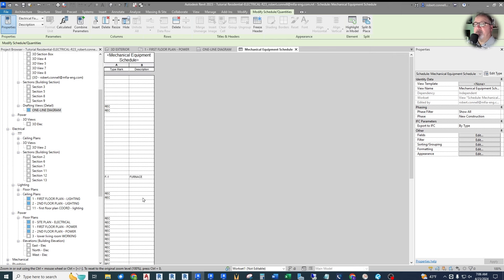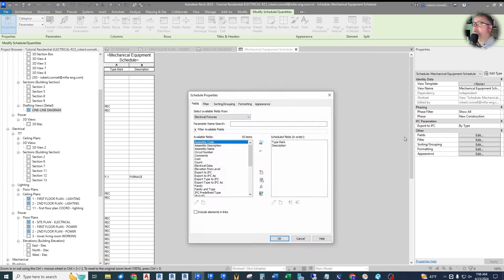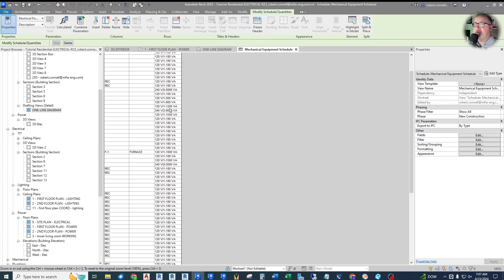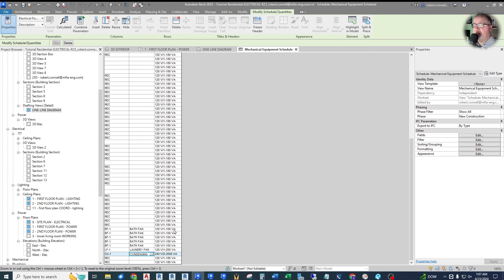The laundry fan and condensing unit descriptions get filled in the same way. Now let's see what else we want to show — I'd like to show the electrical information. Instead of just typing this into a spreadsheet or text box, we're going to extract it from our model. Under Fields, we have Electrical Data as a parameter within our fixtures. Bring that over and we can see voltage, phase/poles, and the actual apparent load in VA. We can see a variety of equipment here, including what appears to be a cooktop and wall oven — but those are kitchen equipment, not mechanical, so we could provide a separate schedule for those if needed.